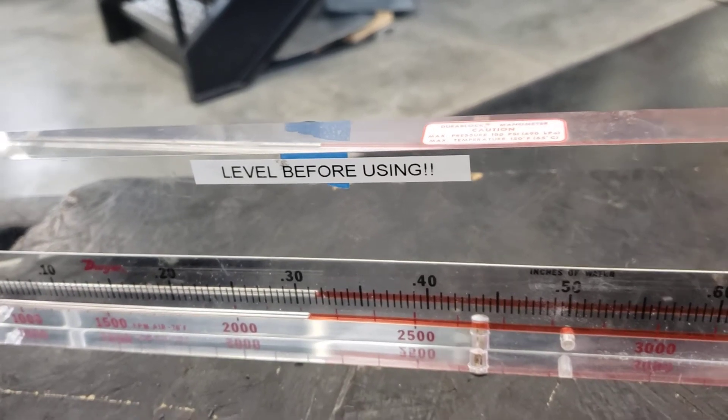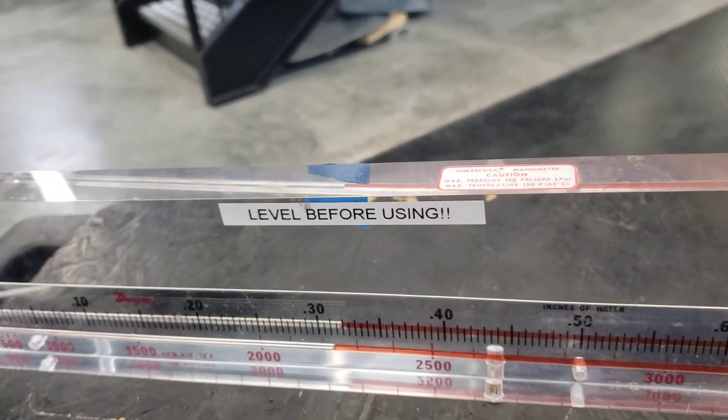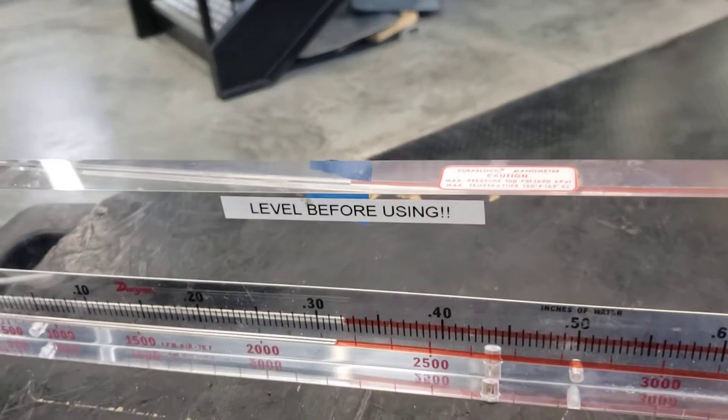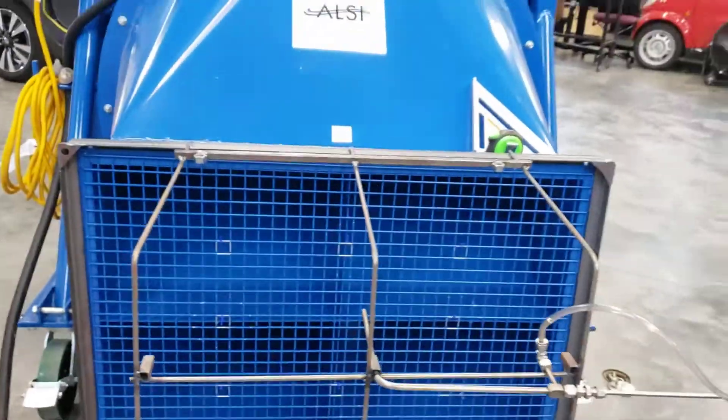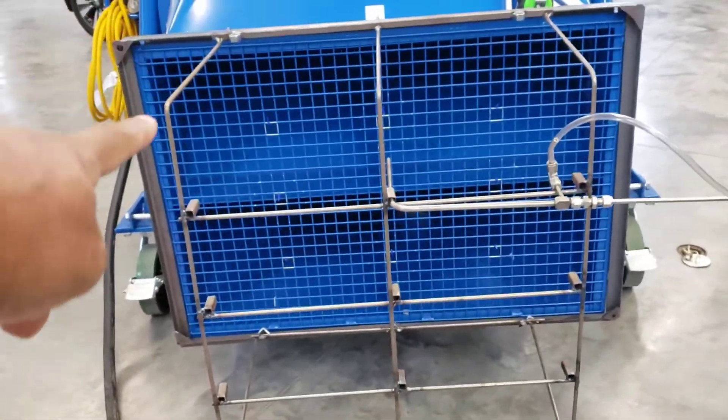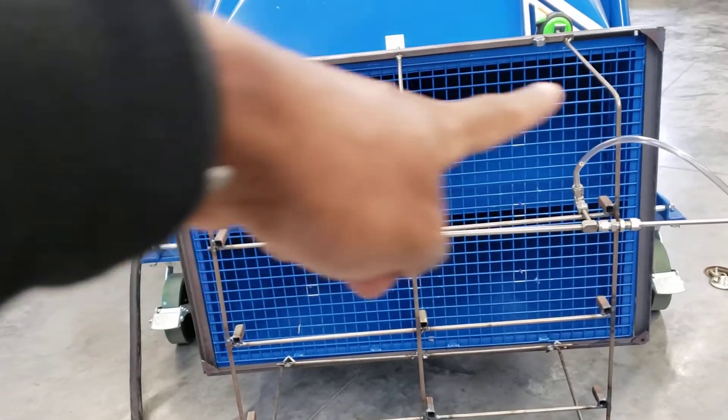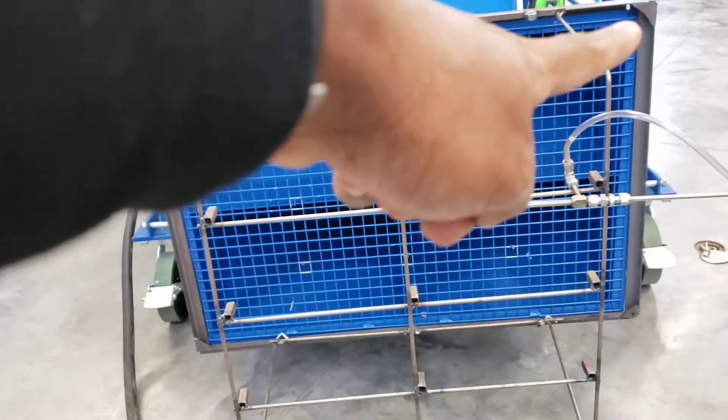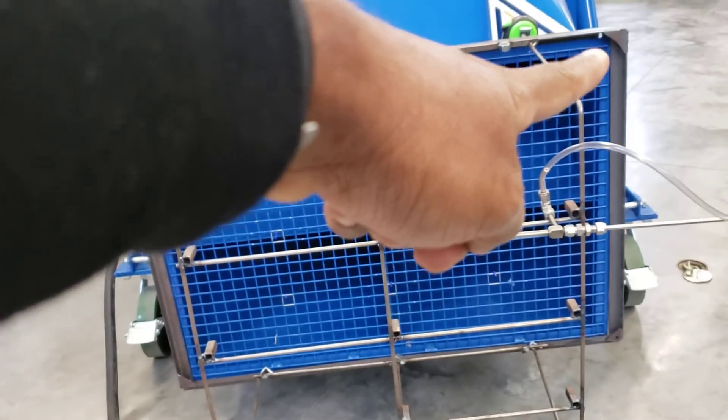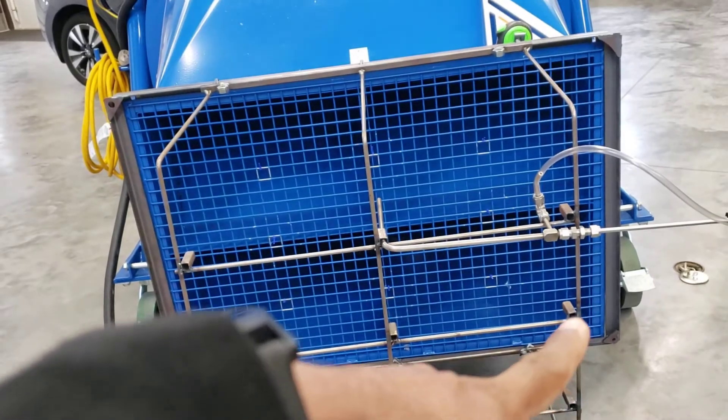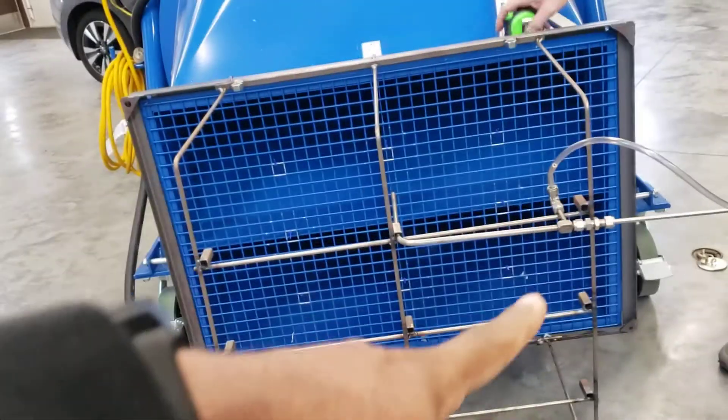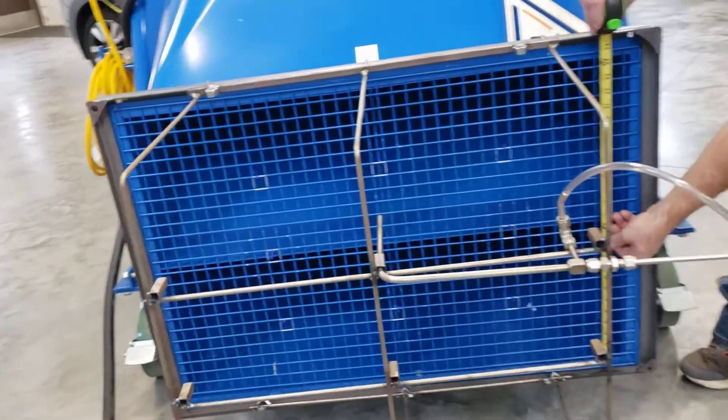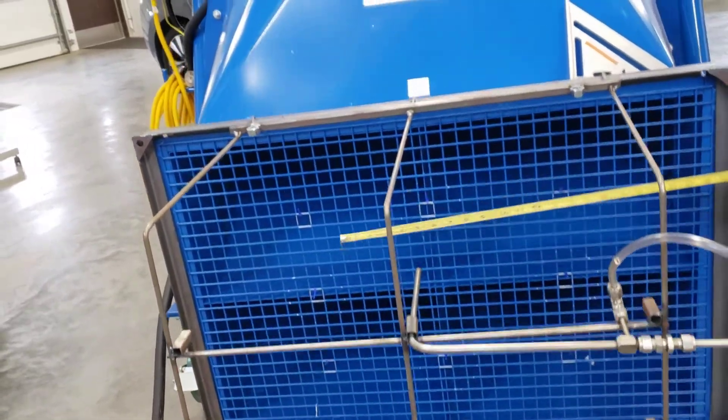To get the velocity, once you get the velocity then you can get the area of this piece, the cross section. You're going to measure from that corner to that corner which is about 36 inches, and that high to there which is about 24 inches.